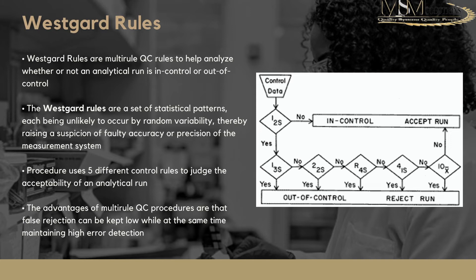If the value is outside the 2s limit, the next question is: is it outside the 3s action limit? If yes — it's outside 3s — you reject the run. That is the first Westgard rule violation. If it is outside 2s but within 3s, you then check the 2-2s rule: is there another value also in that same 2s-to-3s range? If yes, that is a 2-2s rule violation and you reject the run — you essentially have two points between two and three standard deviations.